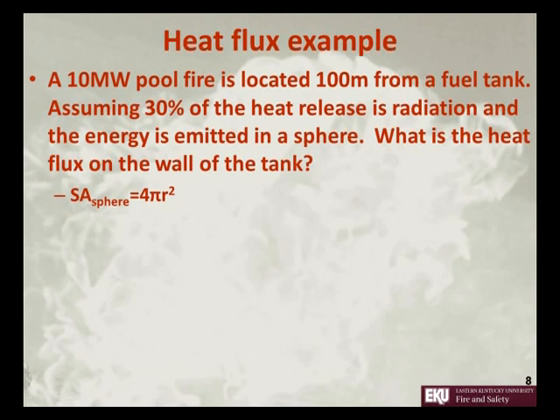Let's do an example. We have a 10-megawatt pool fire located 100 meters from an adjacent fuel tank. Assuming 30% of the heat release is radiated and the energy is emitted in a sphere, what is the heat flux on the wall of the tank?